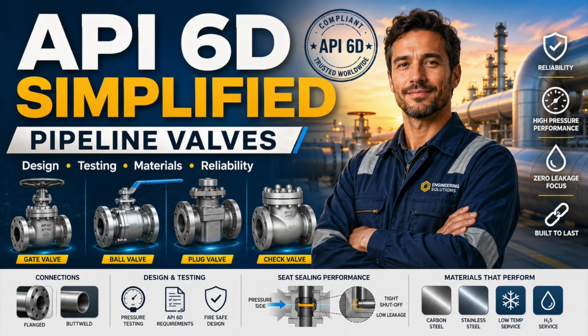A valve described as full bore should still be reviewed against the actual pigging requirement. What is the minimum internal diameter? Where is that minimum located? Is the bore concentric? Does the seat protrude? Are there steps? Are there cavities? Can debris collect? Can a partially open closure element interfere with the pig? Can the position indicator prove full opening? A trapped pig is not a minor inconvenience. It can become a major operational event.